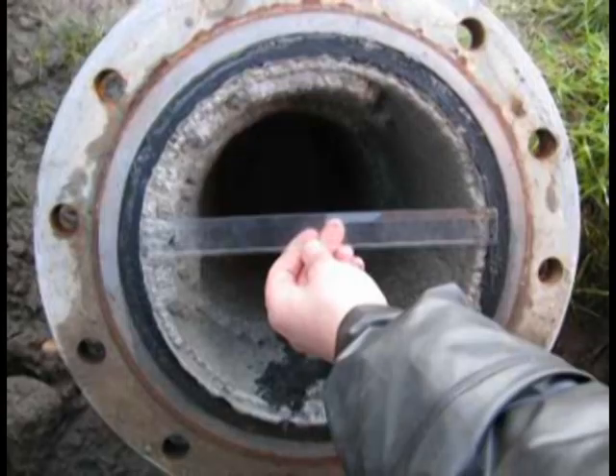So under six inches means there could be some water pressure issues? There could be some water pressure issues, and what we'll do is when the customer brings in their construction plans, we will immediately look it up on our grids. If that line is under six inches, we'll have to ask the customer to give us a couple of weeks to send it up to our engineering department, because we want to be sure the pressure and flow are there before the customer builds and goes to turn on the water and it doesn't work. We want to be sure the flows and pressure are there to operate their fire system and of course their domestic service.